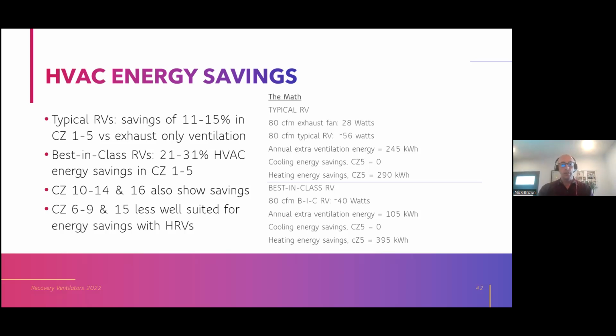And if we're in climate zone 5, there's really no cooling energy savings to speak of in that climate zone. Some of my models don't even show cooling energy use in climate zone 5. So it's all heating energy savings. And in this case, maybe that's 290 kilowatt hours. So we come out 45 kilowatt hours ahead. But with a best in class version, we're reducing that recovery ventilator energy to 40 watts continuous. So we've only got 105 kilowatt hours penalty, and we're saving more because of the better recovery effectiveness. So we might come out 290 kilowatt hours ahead. So you see how the best in class math is working.